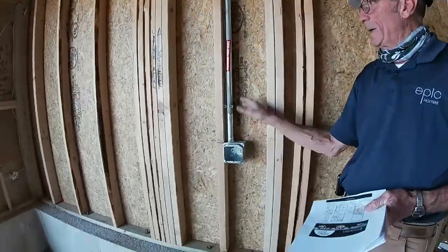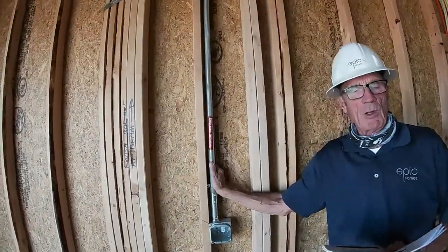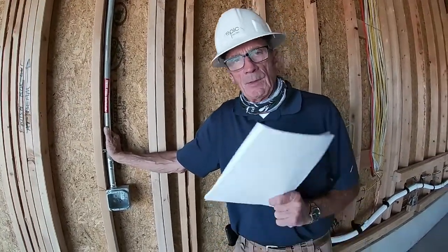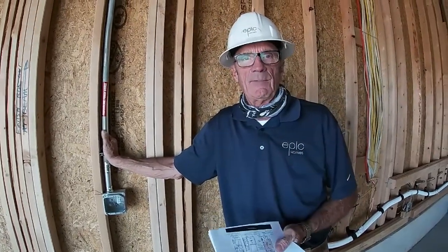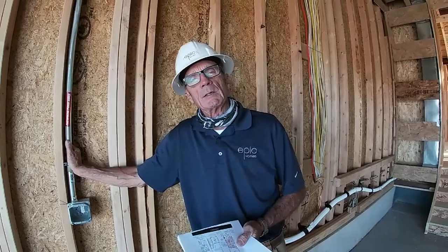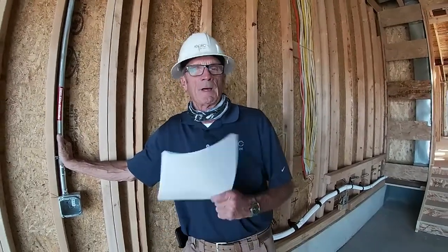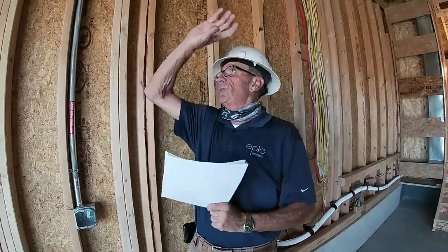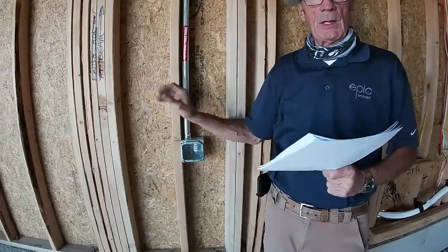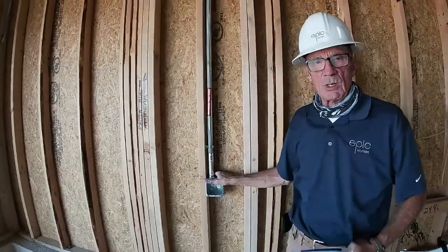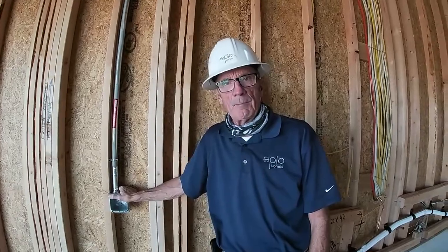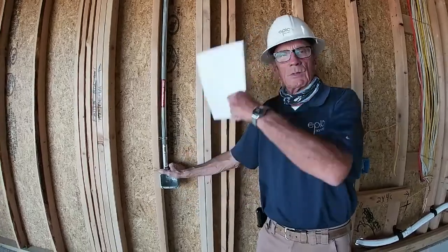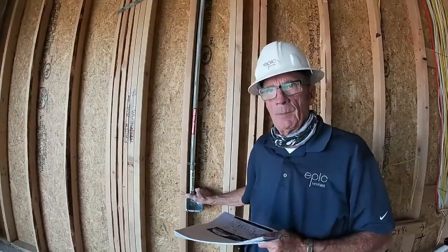This silver box is marked photovoltaic. In every home, we put a photovoltaic conduit from the garage up into the attic. And that's in the event that if you ever choose to have solar panels put on your roof, a solar installer, all his wires go into the attic. Well, he can just fish those down to right here, and it's very close to the electrical connection that he may need. So this is just a conduit or a sleeve or a method for anyone to get wiring from the attic to this location. So this goes up into the attic, and we'll see the termination of that in a bit.